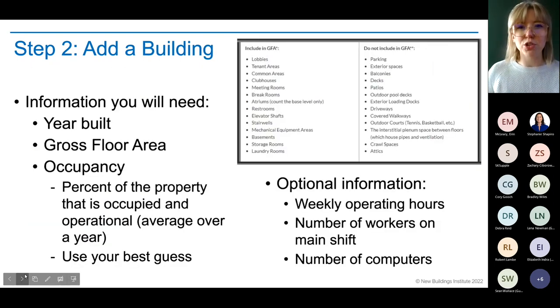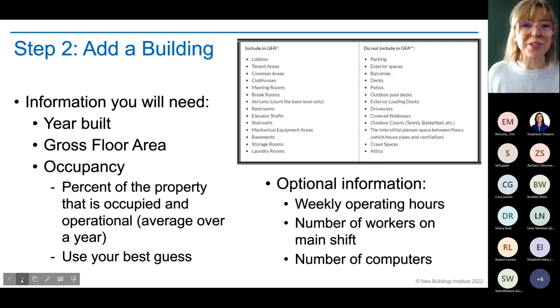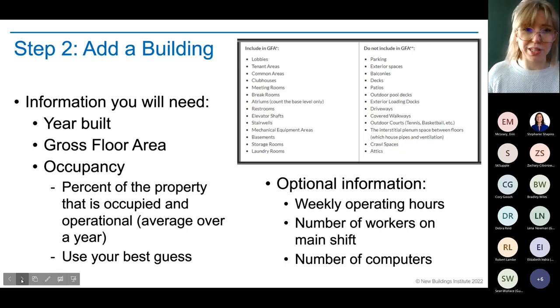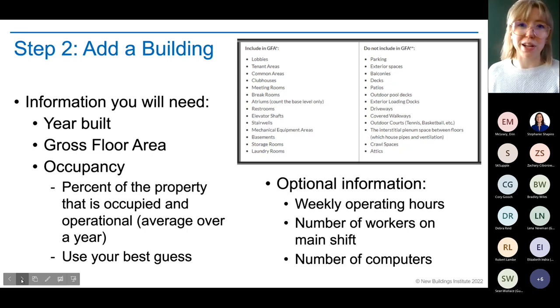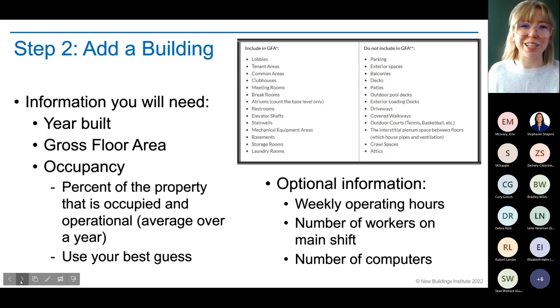In terms of information you'll need: having it ready makes adding buildings much easier. You'll need to know the year your building was built and the gross floor area. The screenshot shows what to include in that gross floor area and what not to include — balconies, patios, driveways, and parking would not be included. The reason they ask for this is to help calculate energy use intensity. You're not air conditioning your patio, so those spaces are excluded.